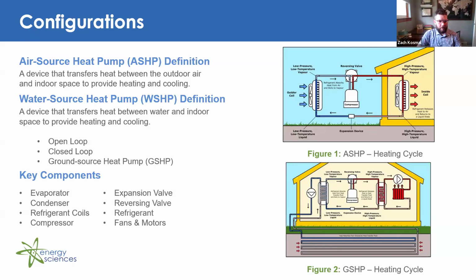You can have two types of ground source heat pumps. You can have horizontal, which as I said is shown in figure 2, in which the piping is laid horizontally at a minimum depth of 4 feet deep. Can vary depending on the application. The other option would be vertical piping, in which U-shaped piping is laid at depths between 100 to 400 feet, depending on the application, and that pipe system has the vertical pipes.